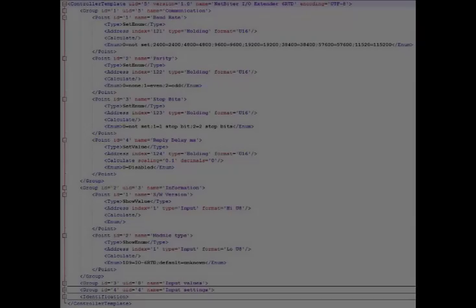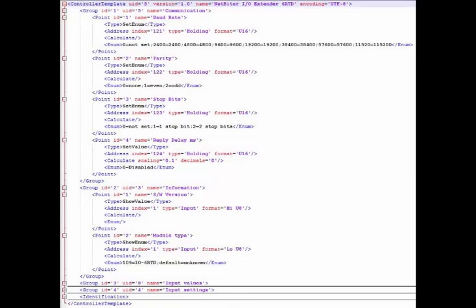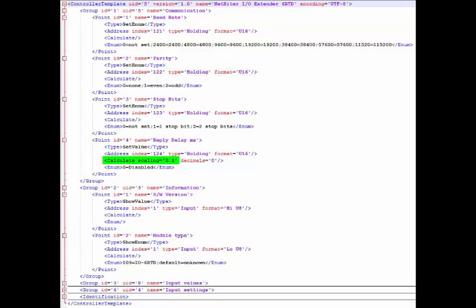A Modbus device template is an XML file describing the parameters for a Modbus slave device. The template contains information about the available Modbus registers and their data types, with scaling and offsets predefined.